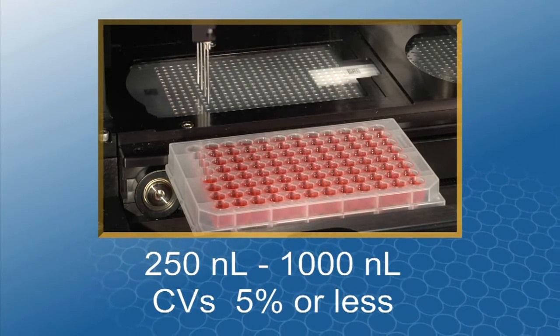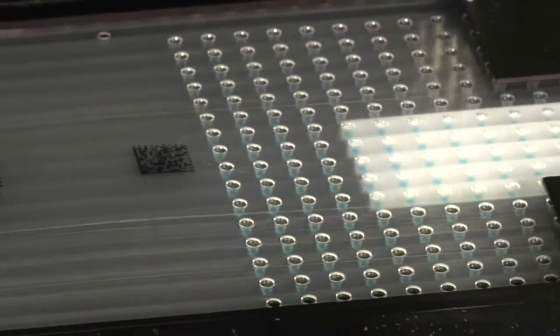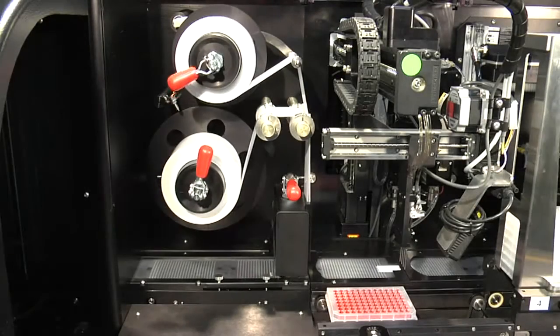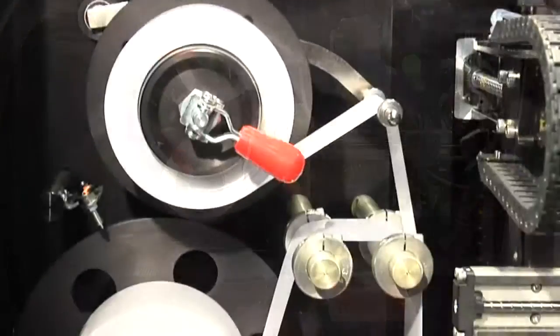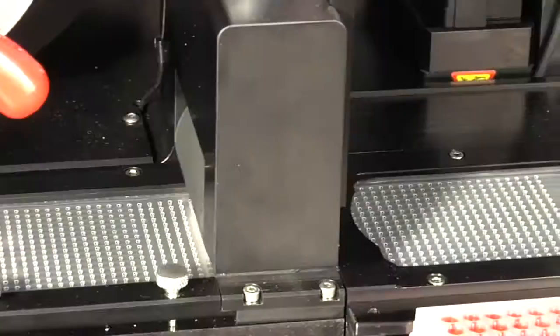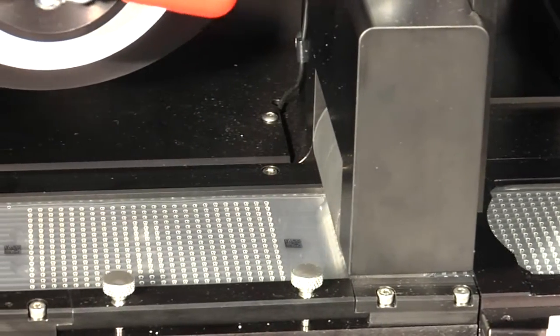You will benefit from a system that is designed to support a variety of isothermal chemistries. Each array is automatically sealed quickly preventing amplicon contamination. During the sealing process, the assay is chilled to as low as 15 degrees within seconds enabling precise incubation time and temperature.